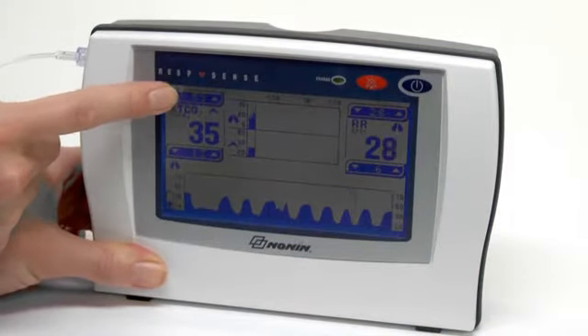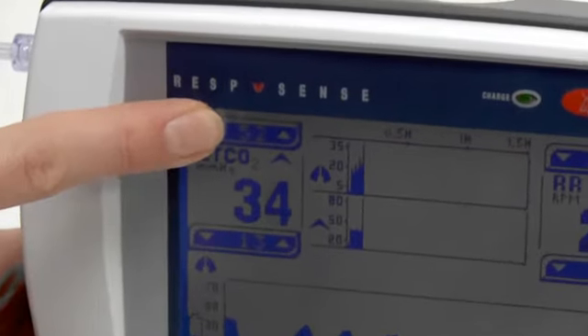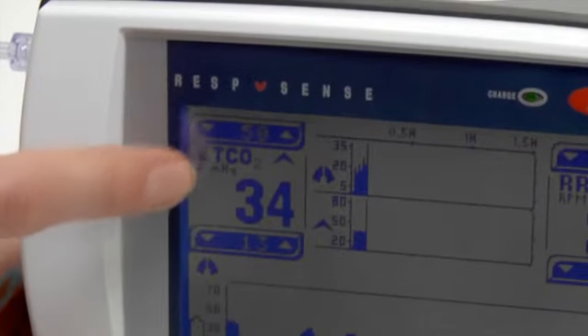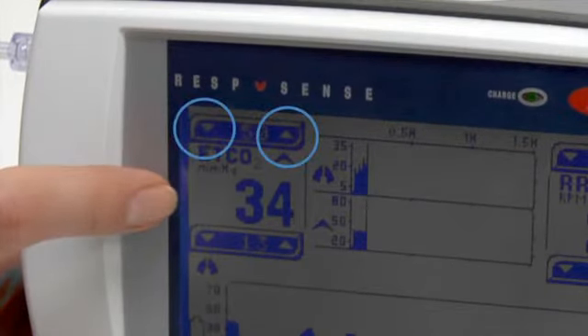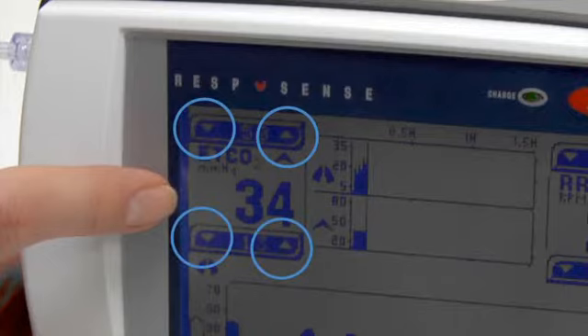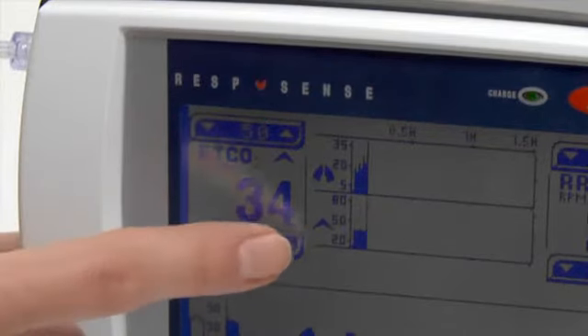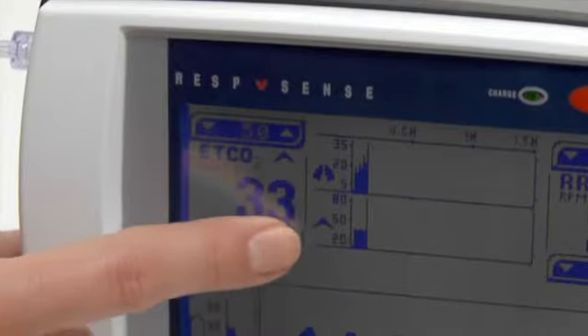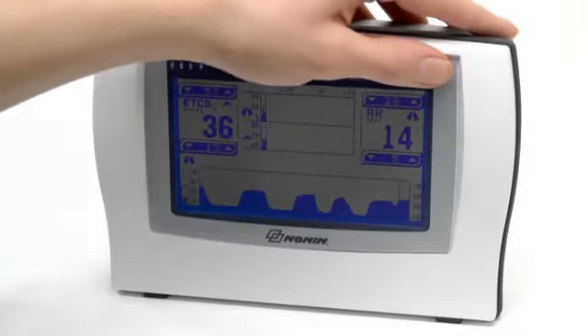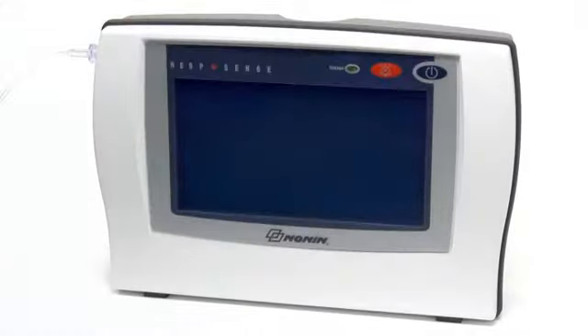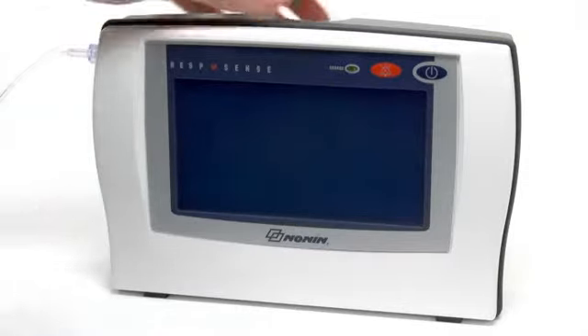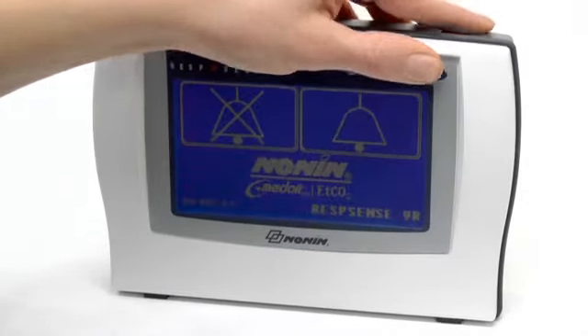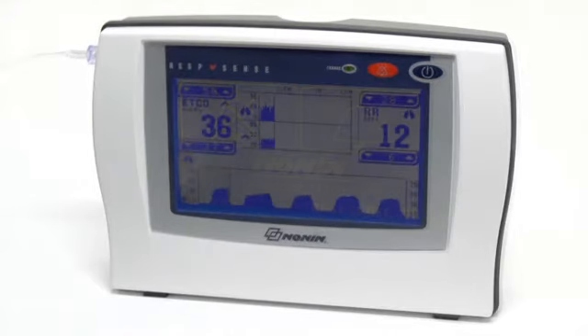Limits are easy to reset. Simply press the up or down arrow in the bar next to each value to scroll or tap to the desired value. Remember, if you turn the monitor off, alarm settings will return to the default limits at the next startup. The monitor is now ready for use and will display data on the screen. You can see the patient's end tidal CO2 value and respiration rate on the display.